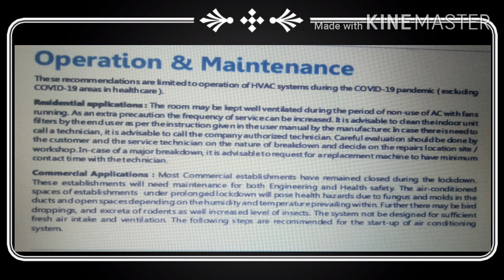The following steps are recommended for the startup of the air conditioning system. The user or owner should get the area sanitized. Study the fresh air and exhaust system adequately as per the guidelines, and inform the user to modify the system if found inadequate. Carry out preventive maintenance on all the units as per the manufacturer guidelines. This should include disinfecting and cleaning of filters, grills, diffusers, and intake surfaces. It is recommended to use a 5% Cresol solution containing 50% Cresol and 50% liquid soap solution. Mix 1 liter of this solution in 9 liters of water. The surface shall be sprayed with the solution, left for 10 minutes, and then washed and wiped clean with a wet cloth. The above methodology applies only to washable filters.